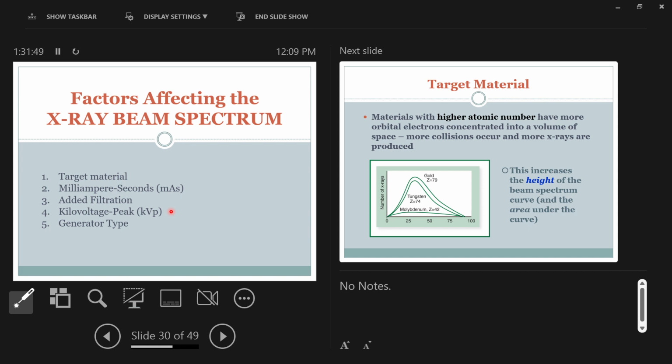You don't change your X-ray tube's filtration. You saw where that fits in the X-ray tube, right? That's like inside the thing, and you got to take the thing apart to get to that. So you don't mess with that, right? You're not taking X-ray tubes apart. You don't mess with filtration. The target material is fixed, right? They're only saying in principle, right?